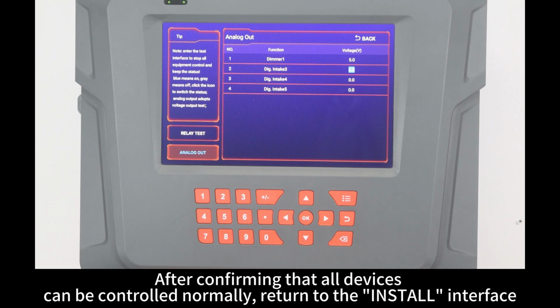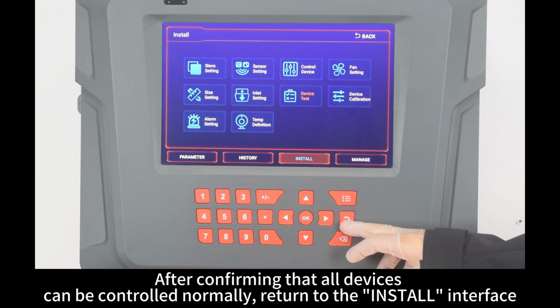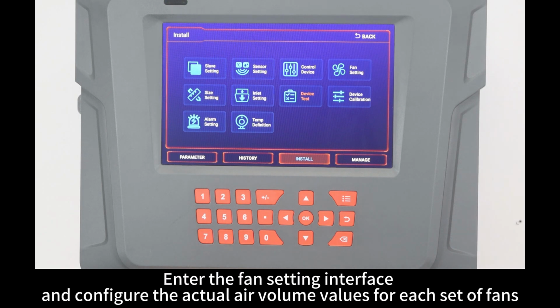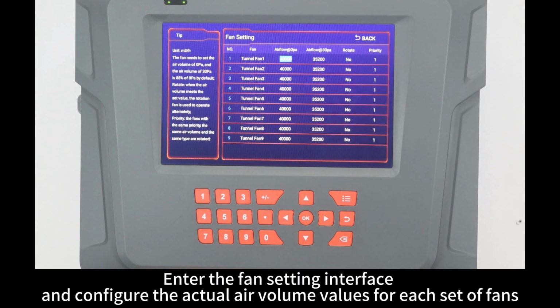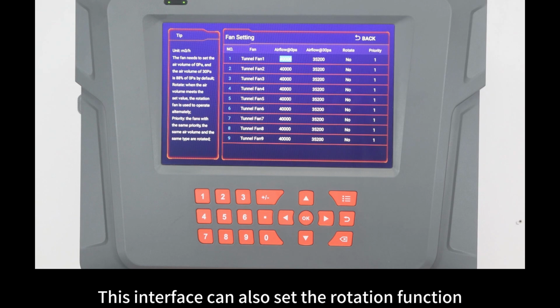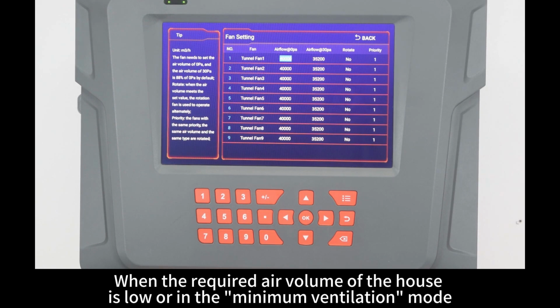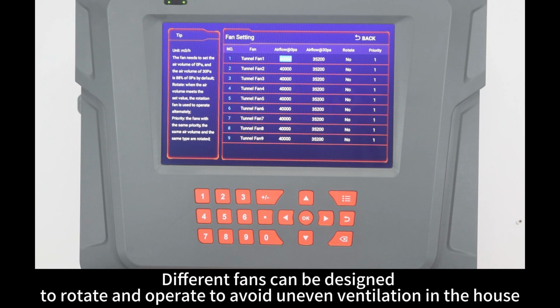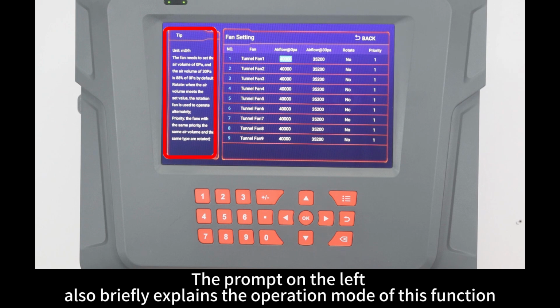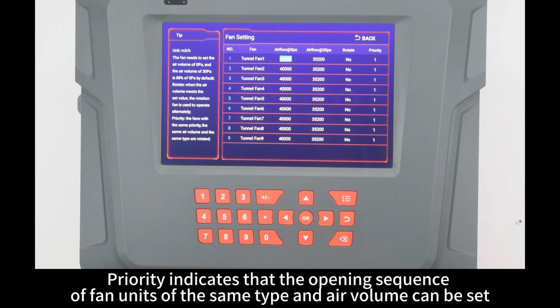After confirming that all devices can be controlled normally, return to the install interface. Enter the fan setting interface and configure the actual air volume values for each set of fans. This interface can also set the rotation function. When the required air volume of the house is low or in the minimum ventilation mode, different fans can be designed to rotate and operate to avoid uneven ventilation in the house. The prompt on the left also briefly explains the operation mode of this function. Priority indicates that the opening sequence of fan units of the same type and air volume can be set.